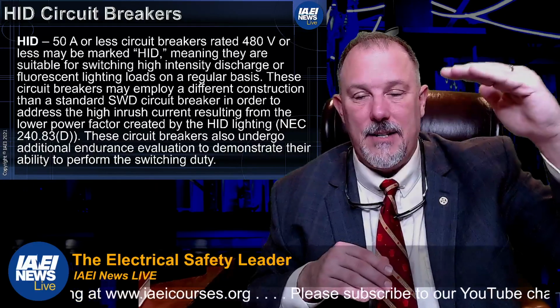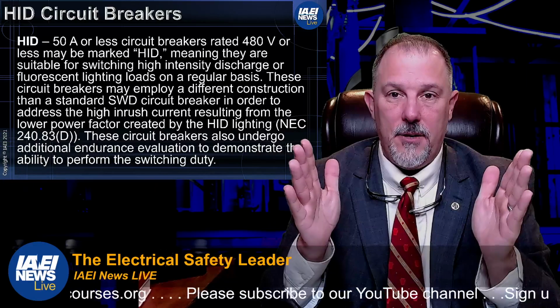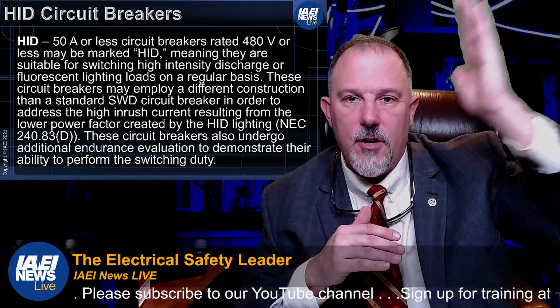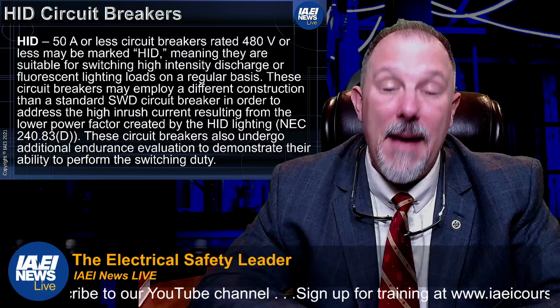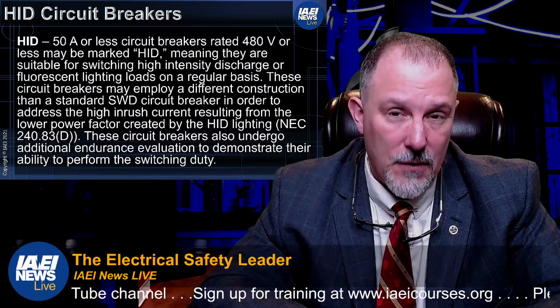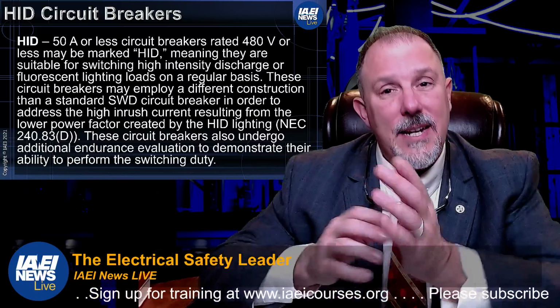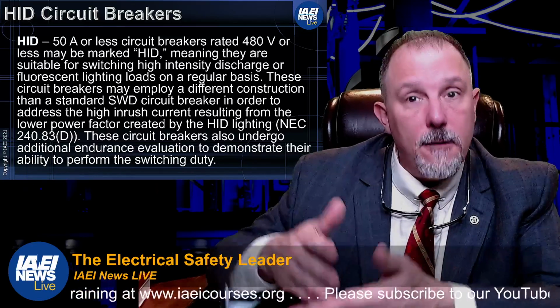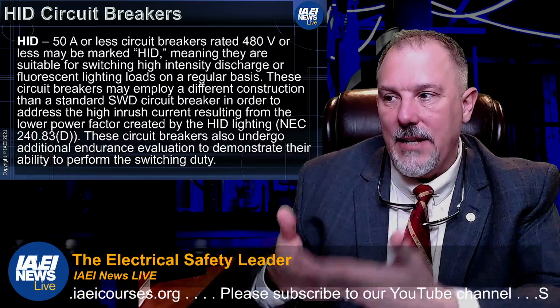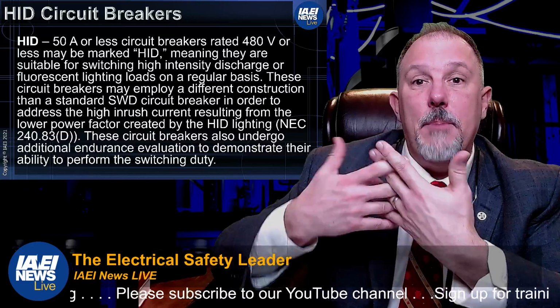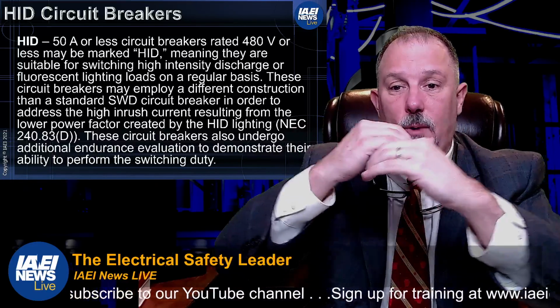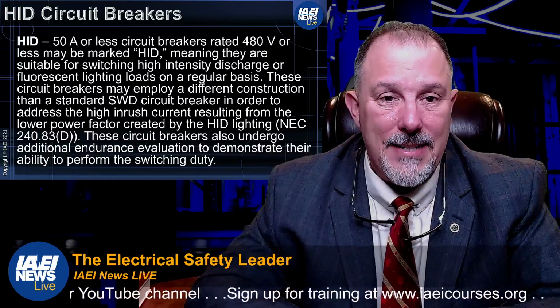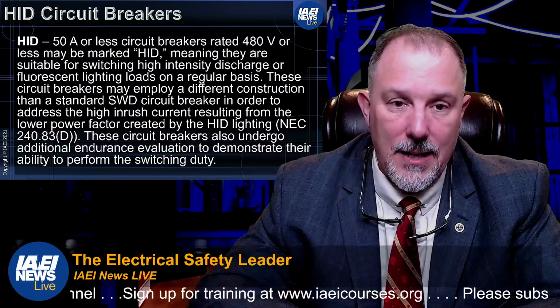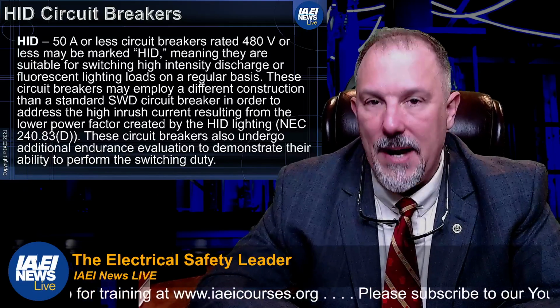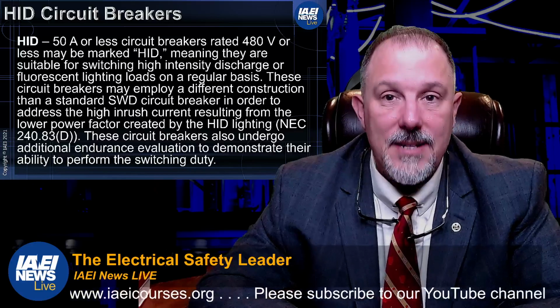When my voltage is low on the sine wave and my current is rising, because they are out of phase with each other, I'm at a lower voltage trying to stop the flow of current at a higher current magnitude. That is a challenge for a circuit breaker or any switch device. So whenever we test switches, we always test circuit breakers at certain power factors. Well, if I'm on a lighting circuit, I need to make sure that my power factor angle, the difference between my two sine waves, is accounted for in how I test it. So a breaker with an HID marking on it means that it was tested with a power factor that you might see with this type of lighting technology.